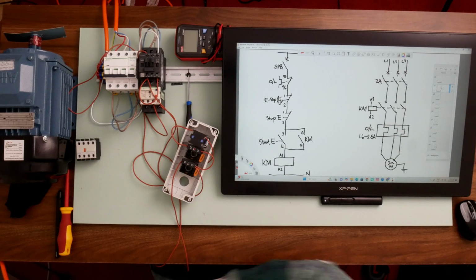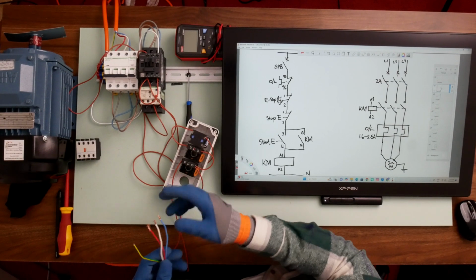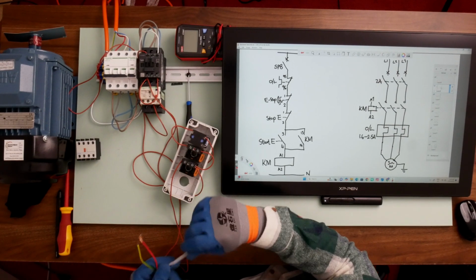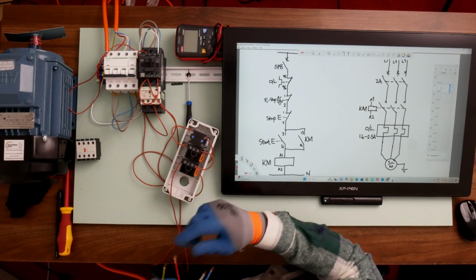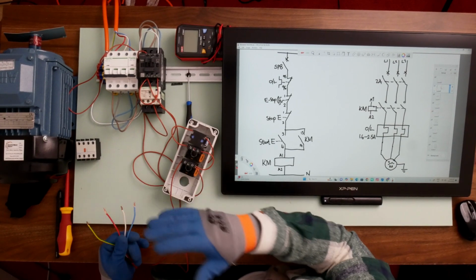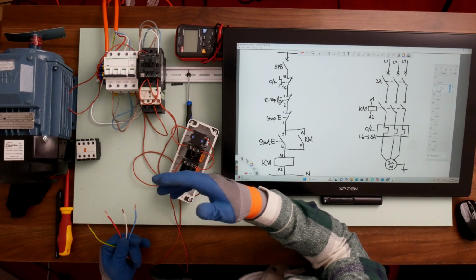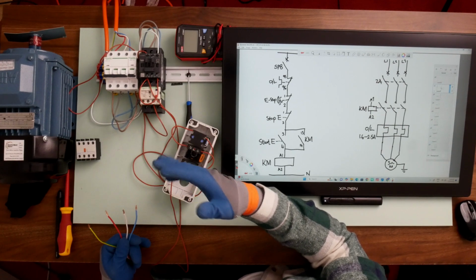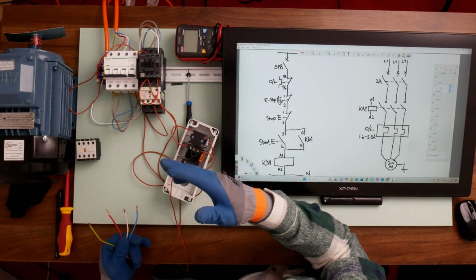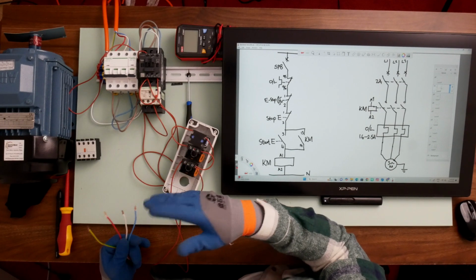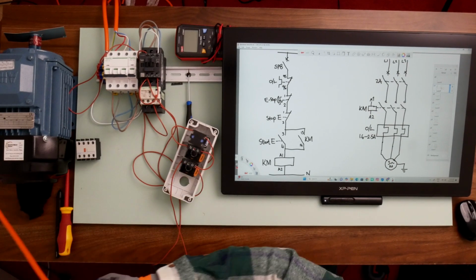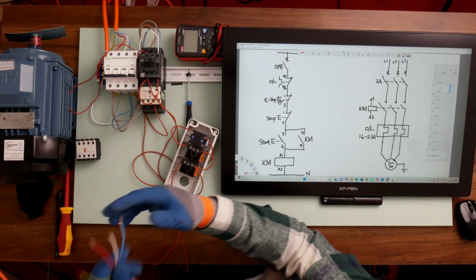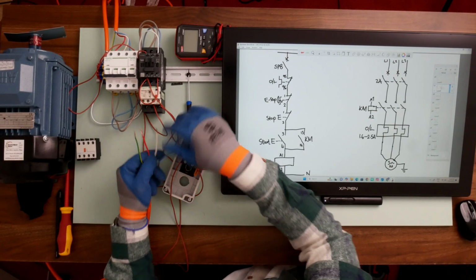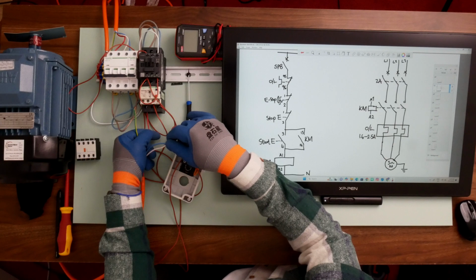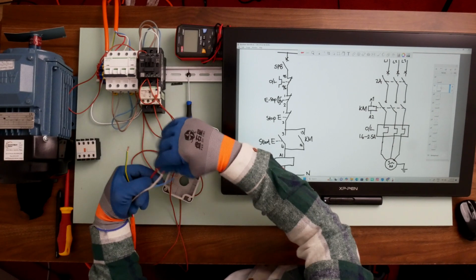Now we're not going to go through the terminal connections in this electric motor. We'll do that in subsequent videos, but if you need to do connections, just follow the instructions that we briefly went through for the delta or for the star connection when you are connecting your electric motor. So this cable is already connected to the motor terminals. So I'll simply connect it to the bottom of my overload relay here, and also make sure that it's safely connected to earth as well.